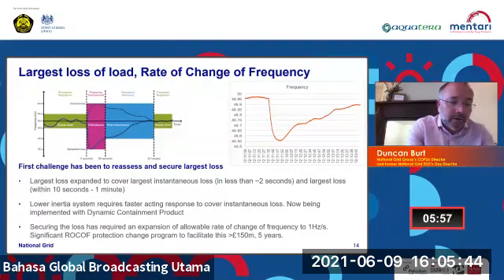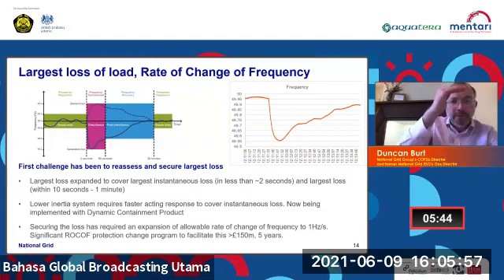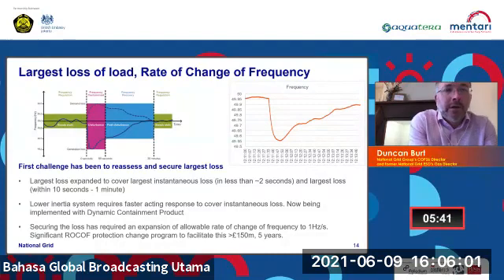Just touching on the first one of those, the largest loss, the way that we handle that is, as you probably know, when you have a steady state system as shown on the left there, when you have a big disturbance, a loss of power infeed, you have a sudden drop in system frequency down towards your operational limit. Our largest loss at the moment is contained for a normal size within 49.5, but for the largest ones to 49.2. And we're expected to be able to secure that within the timescale that the frequency falls, which typically used to be around 5 to 7 seconds, and now will be, for an instantaneous loss, less than 2 seconds.